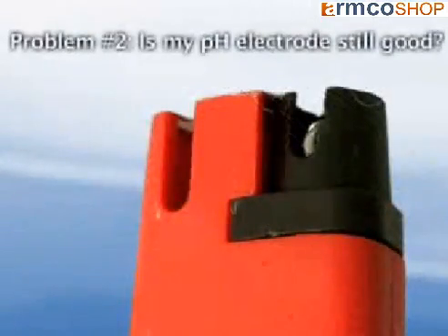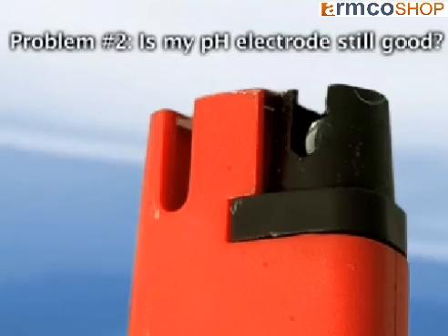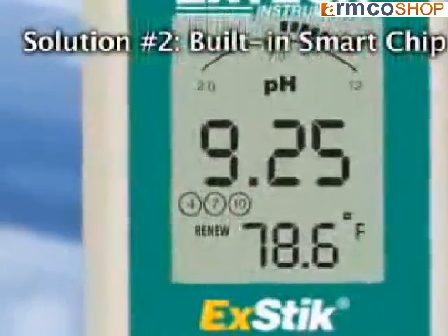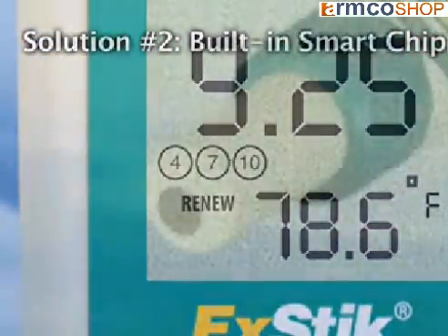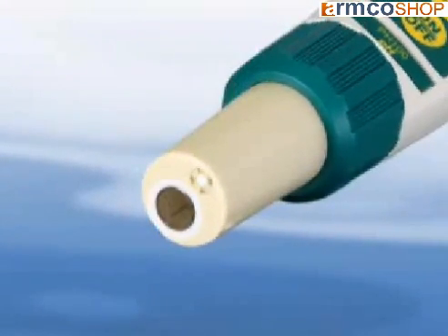Problem number two: uncertainty of not knowing how long the electrode will last and also the shelf life of storing an electrode. Solution: the built-in smart chip alerts the user when to replace or refill the ExStik pH electrode. A renew indicator will appear when the meter senses the electrode not delivering optimal performance, telling you that it is time to service or replace the electrode.